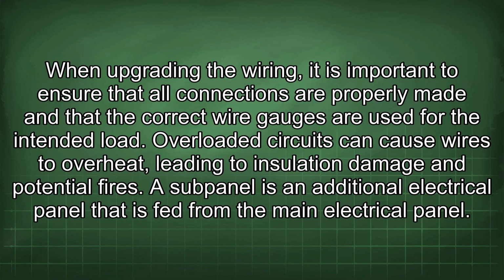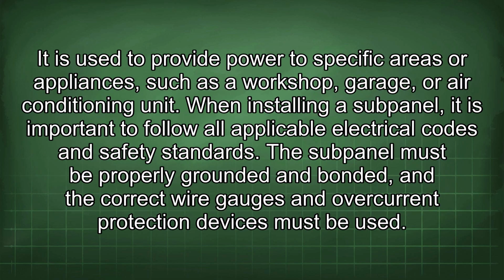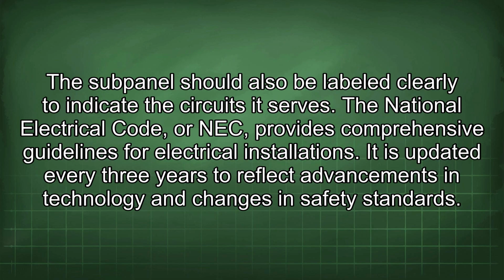A subpanel is an additional electrical panel that is fed from the main electrical panel. It is used to provide power to specific areas or appliances, such as a workshop, garage, or air conditioning unit. When installing a subpanel, it is important to follow all applicable electrical codes and safety standards. The subpanel must be properly grounded and bonded, and the correct wire gauges and overcurrent protection devices must be used. The subpanel should also be labeled clearly to indicate the circuits it serves.